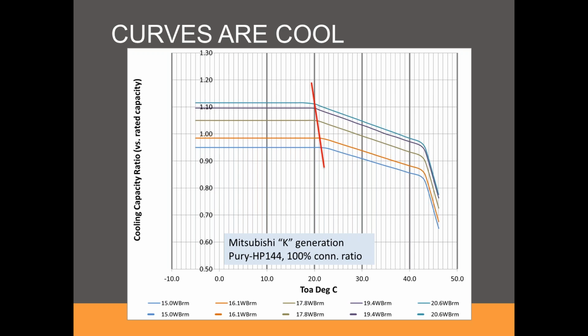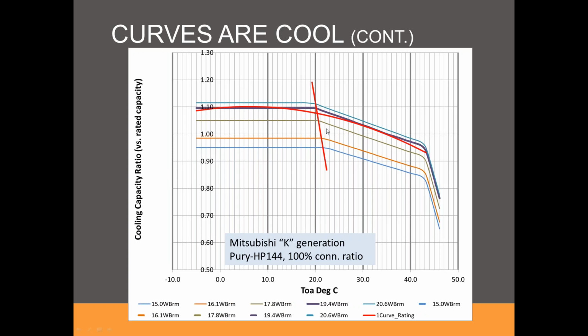That's 12 curves. And then there are others for part load ratio, piping height, piping length, and then the indoor curve or the indoor unit. So there's a lot of curves here. We're going to discuss, David touched on this, you can represent this performance with a single curve. That's the red line. And by the way, it just showed one out of the 5 different indoor wet bulb conditions. But that red curve is not a bad representation of what's going on if you ignore the very high temperature portion here. So for this particular cooling capacity ratio, a single curve representation is a reasonable approach.